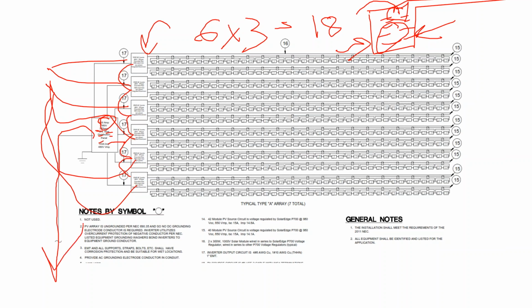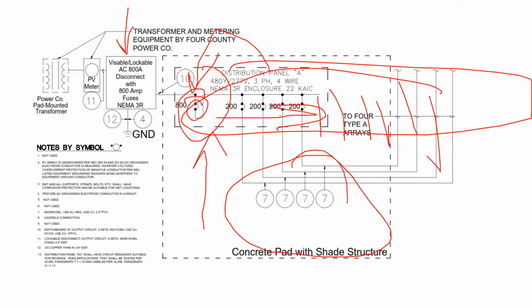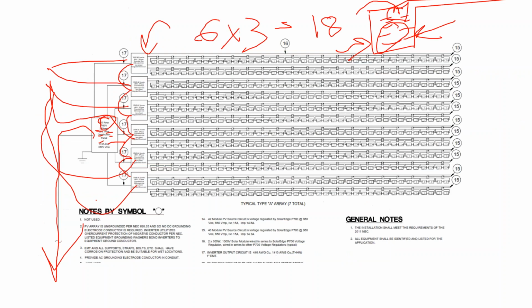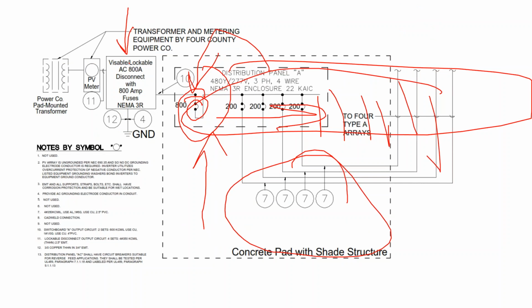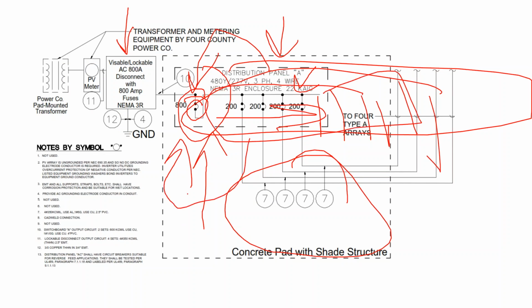Now, by the time we get these panels back to the main, where they're being combined, if we have 7 of these distribution panels on site, if there's 7 distribution panels coming in and each landing on a breaker here, and just kind of ignore the ratings for the time being, but if they're landing on the breakers here and there's more than 6 of them, then we need to have this main breaker.